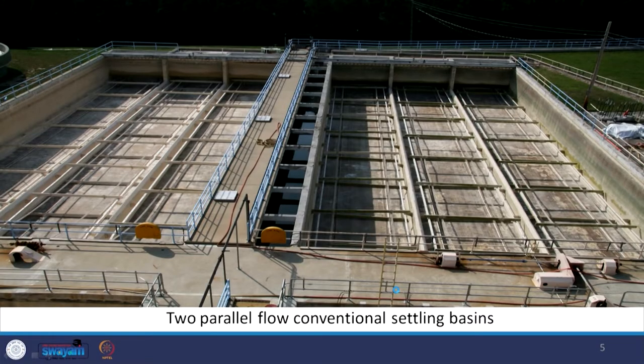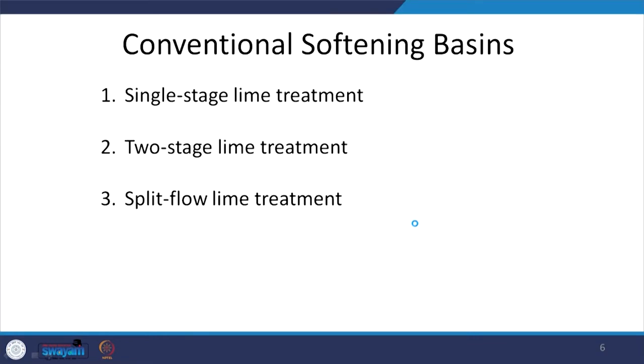And parallel conventional flow settling basins, this is one other aspect. Typically rectangular, long and narrow is something that you want. But then the space beside will be an issue. You can't really use the space beside it. So again, different advantages and disadvantages. But with respect to the theory, if you can channel them into narrow channels, rectangular, long and narrow are the best for sedimentation. So conventional softening basins, there are three kinds: single stage, two stage lime treatment, and split flow treatment.